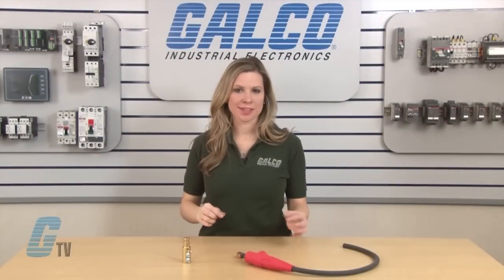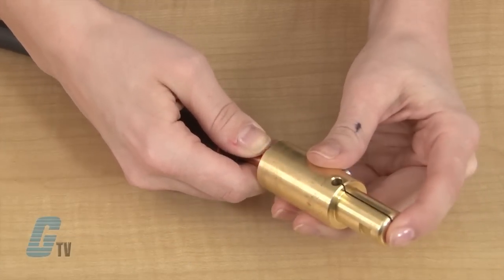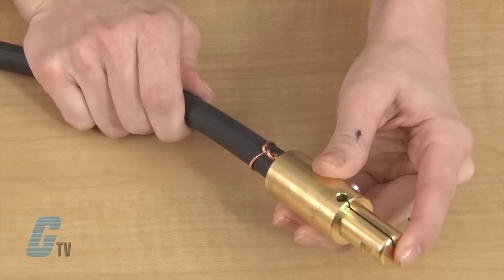When using 4-Aught cable, the strain relief would need to be opposite the drive pin. For all other cables like this one here, the strain relief will need to be placed opposite the set screws.